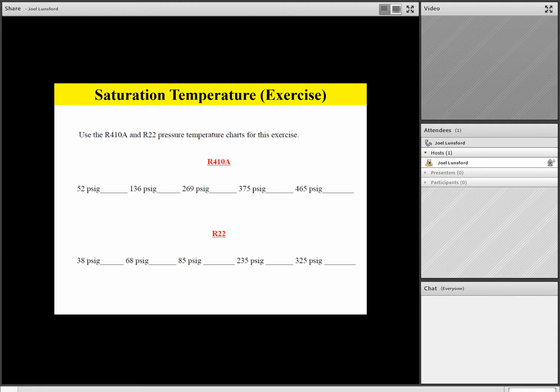So at 52 PSIG on 410A, we see that the pressure temperature conversion is 3 degrees. The next one at 136 PSIG for 410A is 47 degrees. Now team, it's always important that we understand we have to find the pressure temperature relationship off of this chart. So when we start doing some service calls later on, we're going to have to take a suction pressure and convert it to temperature. We're going to have to take our discharge pressure and convert it to temperature. And this is what this practice is all about at this time.